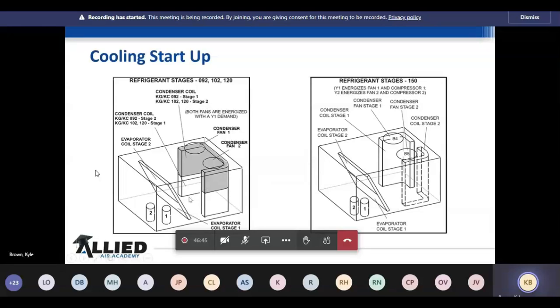So if you happen to be just wanting to check stage 2 and you're not running stage 1 for some reason, that condensate water, number 1, it's not going to flow correctly when it hits the dry part of this coil. It's going to pull off and you're going to have water damage. Number 2, you're going to have airflow issues because the air is going to take the path of least resistance. So it's going to go through this bottom part of the coil much quicker than it will the top. And if you're checking refrigerant pressures, you're not going to get an accurate reading anyway. So you've got to make sure both compressors are running.